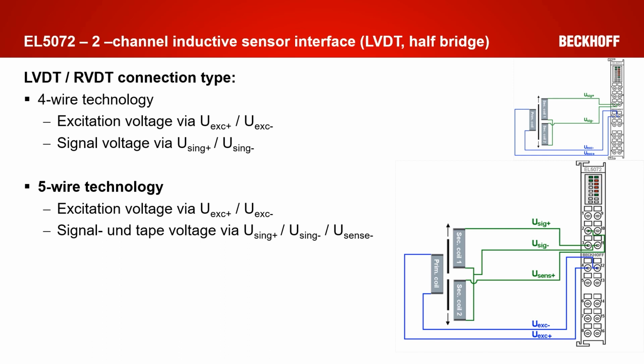This can be achieved because of the systematic compensation of disturbing influences, for example, some temperature drifts, deviation in the excitation signal source, but also different complex factors of the secondary side, and also more common disturbances in the signal can be compensated. With this measurement method, the voltage that is measured is independent of the excitation voltage, so temperature dependencies of this source are not relevant. There are also some sensors with 4 wires on the secondary side. In this case, we recommend connecting 2 of these wires of the coils as close as possible to the probe to realize a center tap and to enable a 5-wire measurement.